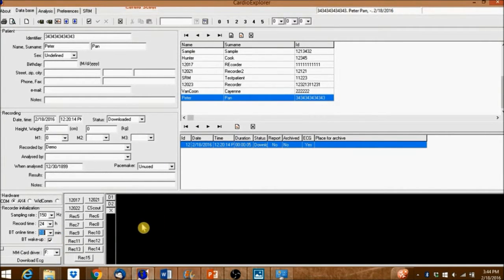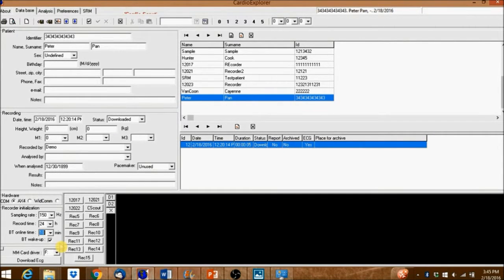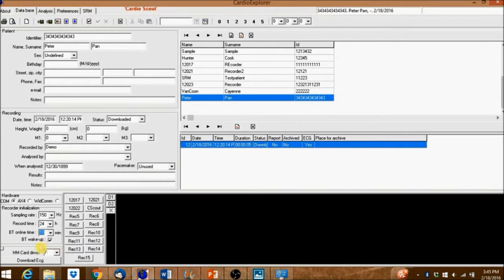This will allow you to see the live stream for 10 minutes. After 10 minutes, the Bluetooth radio inside the recorder will shut down to save battery, and you will not be able to see the live stream in the online window anymore.